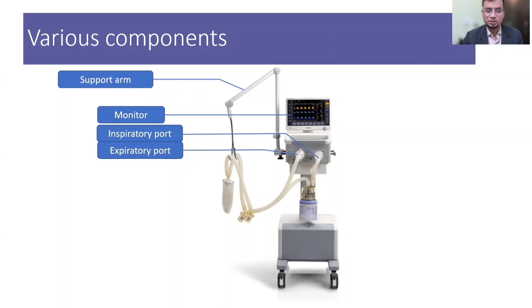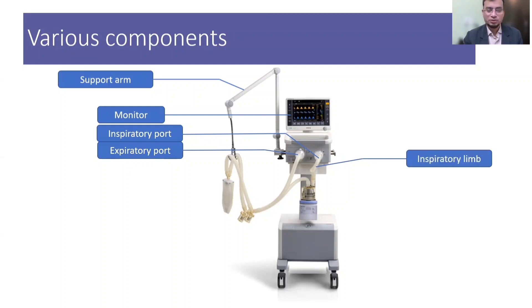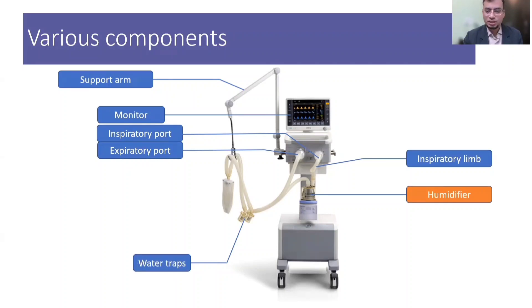The inspiratory limb is a part of the breathing circuit that is connected to the humidifier, where gases are heated and humidified before delivery to the patient. This is the inspiratory limb, and from the humidifier gases go to the patient. In the breathing circuit there are two traps called water traps, which collect the condensate from the circuit.